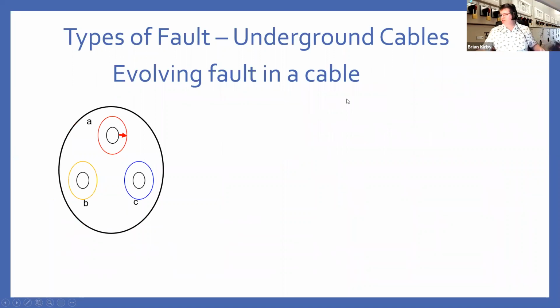So if we look at cables, I mentioned insulation failure. So say you've got a cable that's been running for a number of years and the insulation has started to fail on the A phase, and you start to get a fault developing on that phase. The way these typically appear is you'll get a crack in the insulation, moisture will penetrate the crack, the voltage on the line will then arc across it, causing a spike, but that spike will vaporize the water, driving it out of the fault, and the fault will clear. And then the process will repeat itself sporadically, and gradually, every time it happens, the insulation deteriorates further and further.